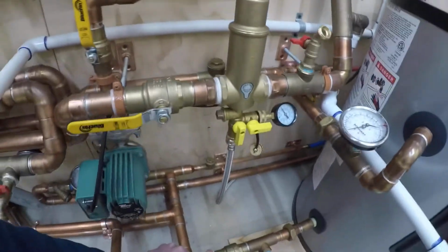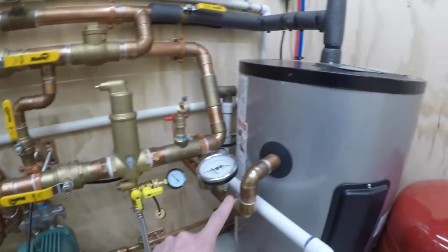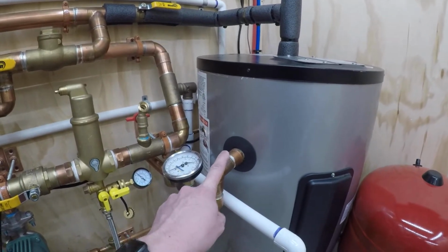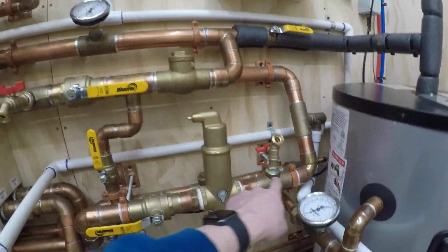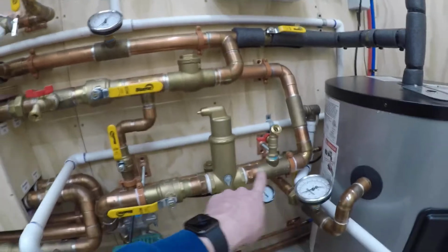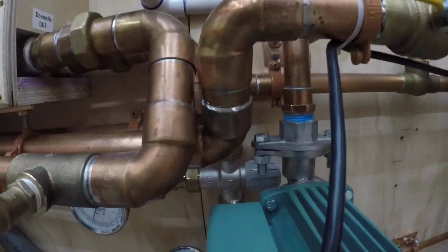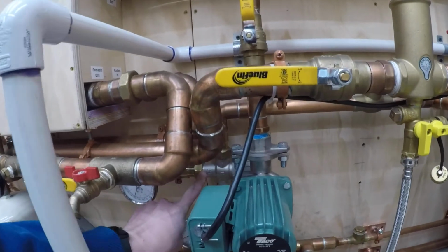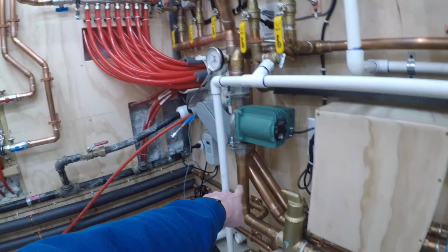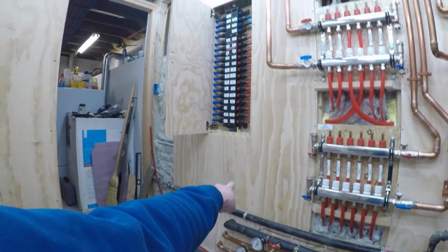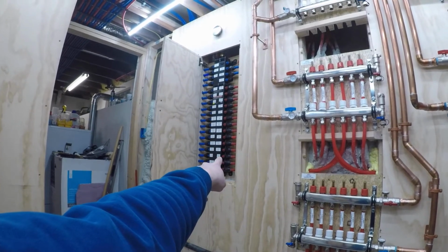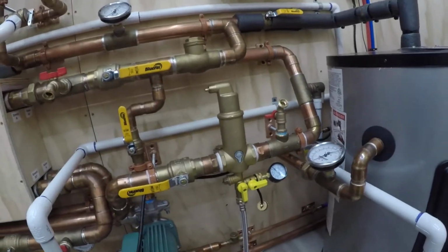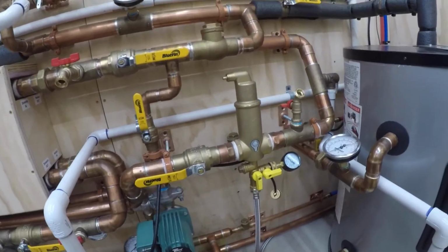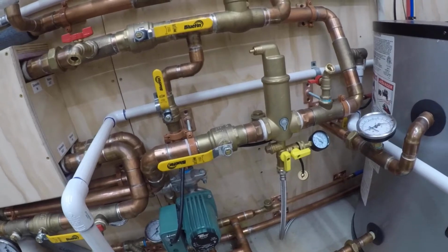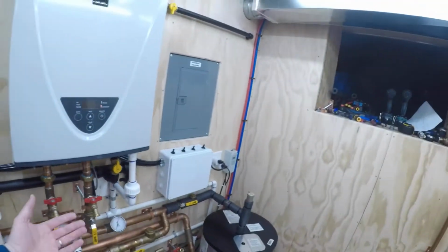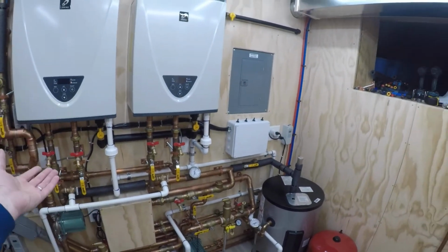So if there's a call for hot water, the domestic hot water comes out of the tank right here. It goes over back there, tees off back there, I don't know if you can see that, comes over and goes into the hot side of that three-way mixing valve. Then on the output side, the mixed side, that runs all the way over along that top line, up and into my supply for my fixtures. So if somebody upstairs turns on the hot water, the difference between this system and our old tankless system is that normally the tankless water heater would fire. It would have to turn on to heat the water.